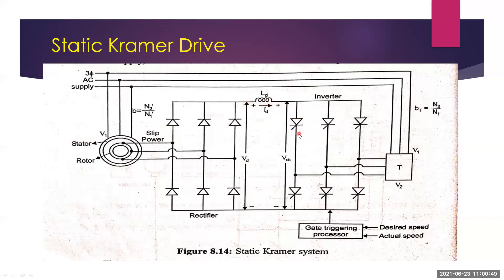The rectified DC voltage is fed to the inductor, which suppresses ripples and harmonics, producing a smooth output that is fed to the inverter input. The DC power is converted into AC power by using a line-commutated inverter. Both the rectifier and inverter are commutated by alternating EMFs appearing in the slip rings and supply bus bars respectively.